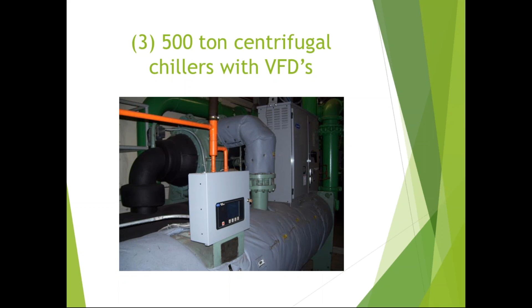It has 3 500-ton centrifugal chillers, upgraded 2 years ago with frequency drives. This supports the 24/7 chilled water operations. The chilled water system has condenser water pumps, 100 horsepower, across the line with no frequency drives on them. Frequency drives are on the tower fans instead.